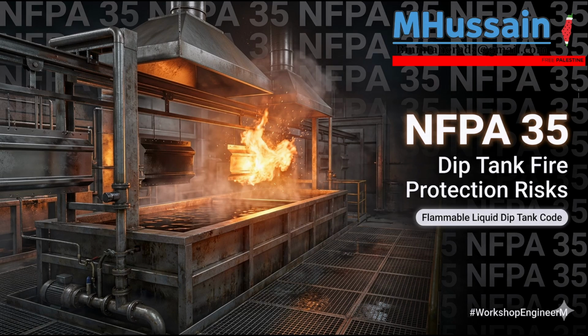Yes, and this is where the physics of explosions dictate the real estate. Those baseline numbers are for stable liquids in vessels, where the emergency relief venting is set to 2.5 psi or less. Wait, why 2.5 psi specifically? Because if a vessel is exposed to fire, the liquid inside boils and pressure builds. If the relief vent pops open at a low pressure under 2.5, it releases the vapor relatively gently.